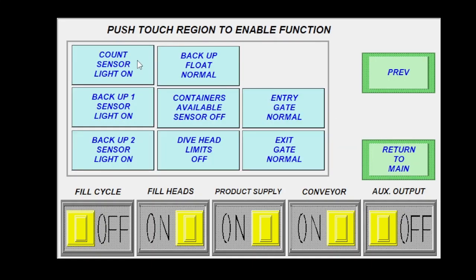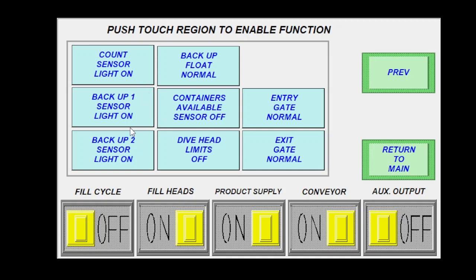Next is going to be for our count sensors. You can change these so if you do replace the sensor later on, you can change whether it's light on or dark on because some sensors don't have the ability to be switched with wiring. So you can do it here in the program. Same thing with our backup float. You can change it here if you needed to. Containers available sensor, if you want that to be off or on. We do not use dive head limits. So this is off.